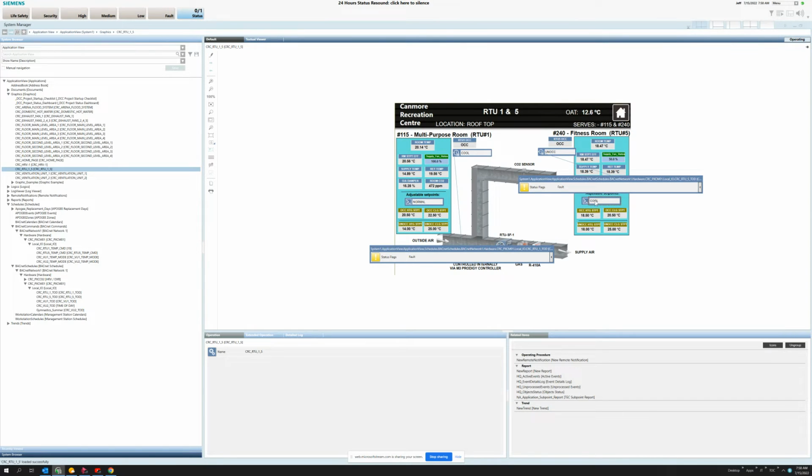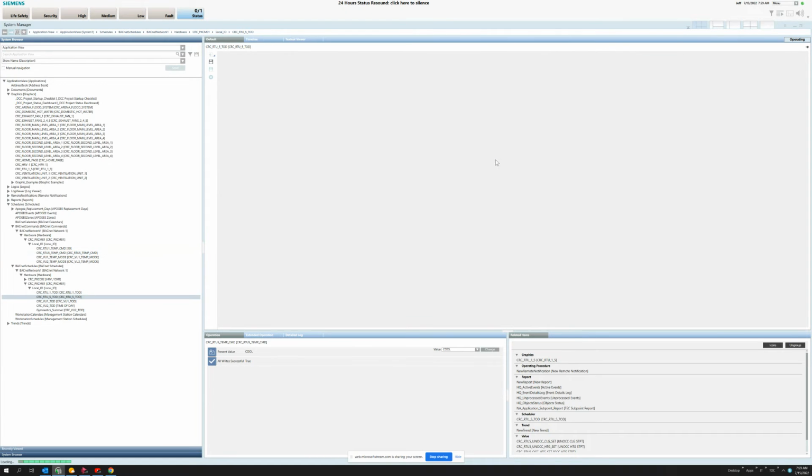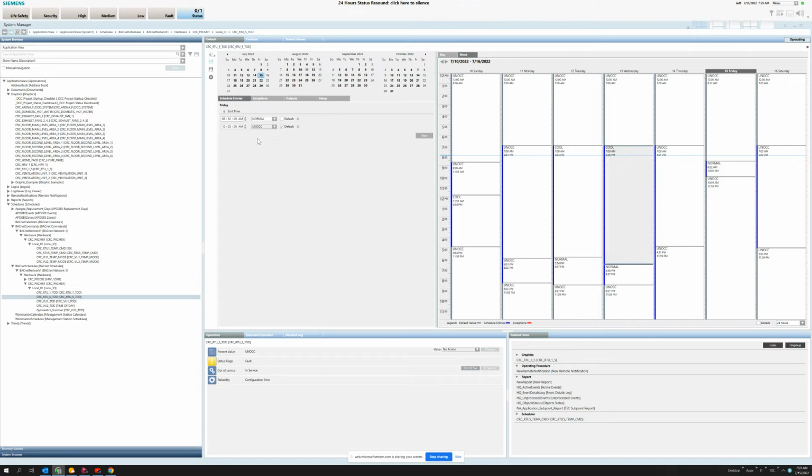However, on 240 RTU5, this one is also throwing faults and inconsistent. Like this one, it's been quite a while since I changed, but this one is respecting the temperatures in the table. So it will update the heating and cooling set points, it seems, to show what's in the table. So, we've got 18 and a half and 20 and a half, and that is reflected in the schedule. So this one, it will, for the most part, do what it's supposed to.